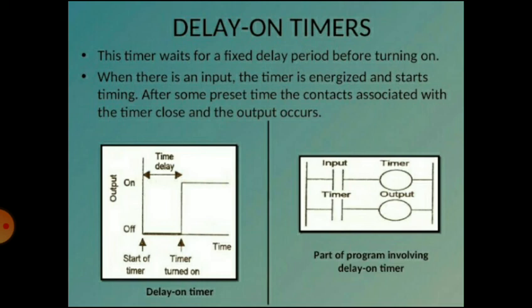The PLC timers are output instructions that activate or deactivate a device after a preset interval of time. PLC timers offer the advantage that their setting can be altered easily, or the number of them used in a circuit can be increased or decreased. In fact, the timers count seconds or fractions of a second by using an internal microprocessor clock. They are used to delay the operations of PLC outputs or to hold the outputs energized for a preset time.